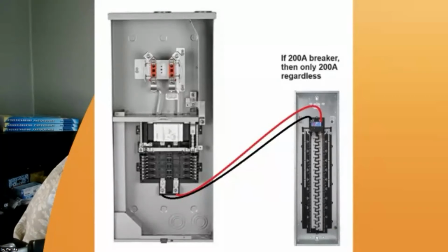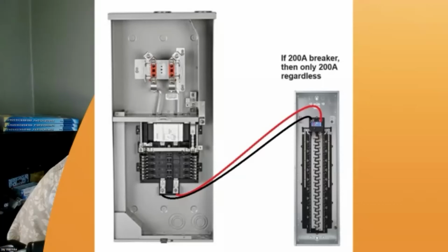I'm now saying don't worry about the bus bar that's inside of your breaker panel. Now go to the left inside of your meter socket. I know. Yeah. No, I understand your logic, and that's where I started with all of this. Is what's different? Well, what I'm saying is different is you're never going to pull through that bus bar in your emergency disconnect more than the breaker in your service panel. Oh, I see what you're saying. So 200 amps is the max that's ever going to flow directionally towards your house.